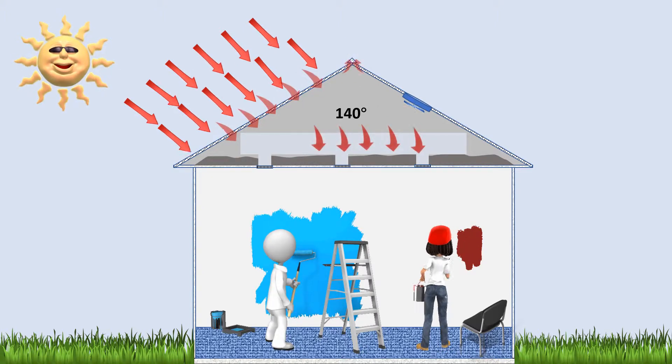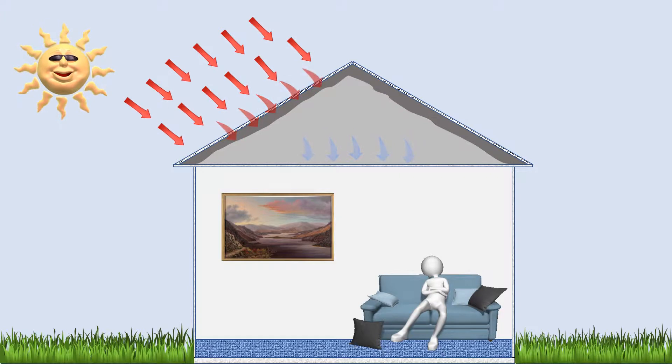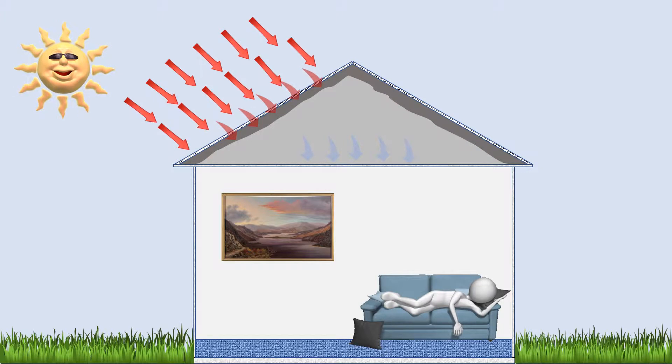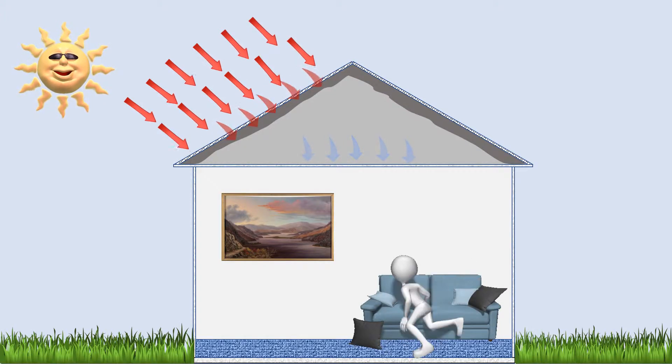Now let's take a look at option two. If we put the insulation under the roof deck, which is typically done with a spray foam material, we stop the heat—or at least the majority of it—from even getting into the attic. On top of that, if the duct work is in the attic, the attic will be much cooler, greatly reducing the load on the duct work.